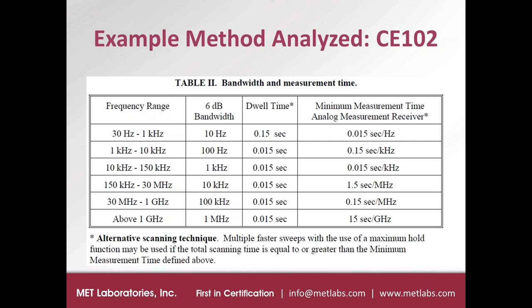So this is Table 2 from MIL Standard 461 that shows different frequency bands and then the resolution bandwidth setting that should be set on the spectrum analyzer for those bands. The next column indicates the dwell time. The dwell time column is for digital spectrum analyzers at each step, which corresponds to each point of resolution on the display of the spectrum analyzer. That's the dwell time required at each step. The far right column is if you were using an analog instrument, it tells you the dwell time per amount of frequency, either hertz, kilohertz, or so on.